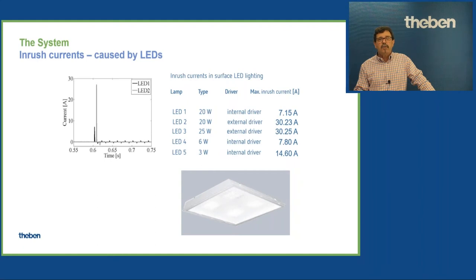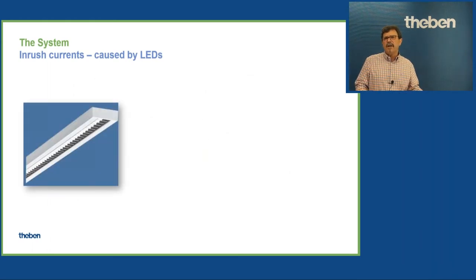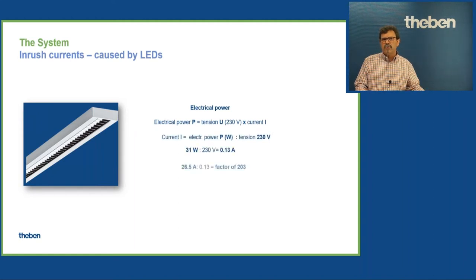This case was not measured in our VDE laboratory, which we have indoor here in our company. This investigation was done by the University in Eindhoven. So that means a totally independent authority. This is a specific university technique, and they confirmed as well what happens here in the background. A small glitch, a small high inrush, which you do have. We are talking about some 100 microseconds. It's rather short, but tremendously intensive. And this finally stresses such kind of relays, which you do have here in motion detectors, in presence detectors, or in controllers, or in, for instance, KNX products.